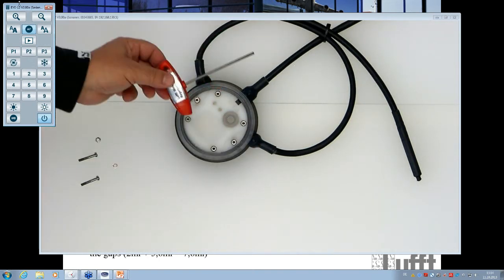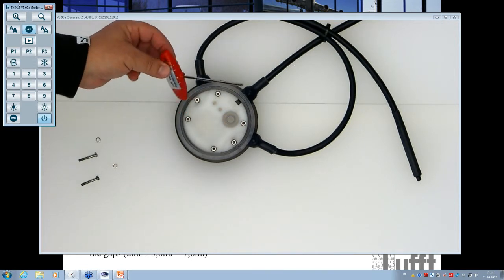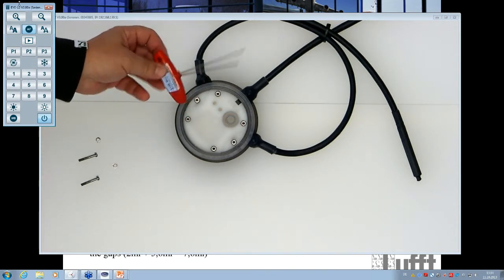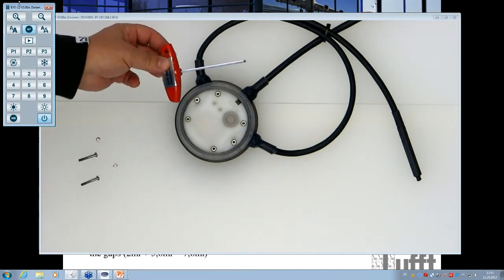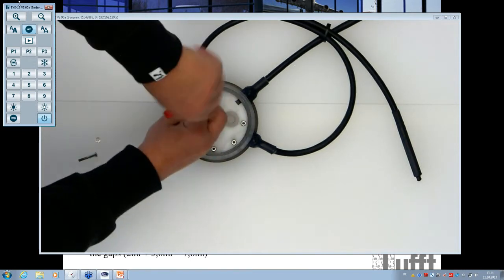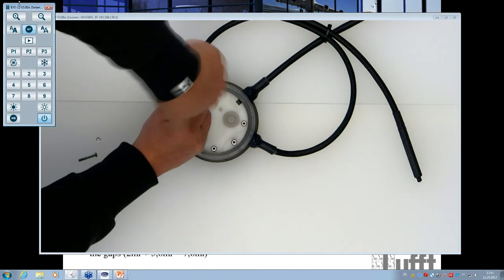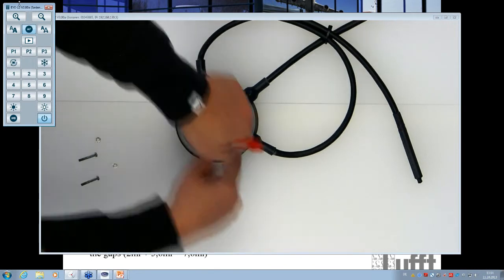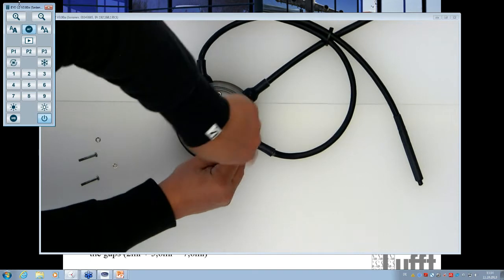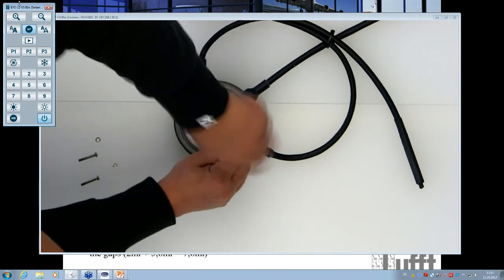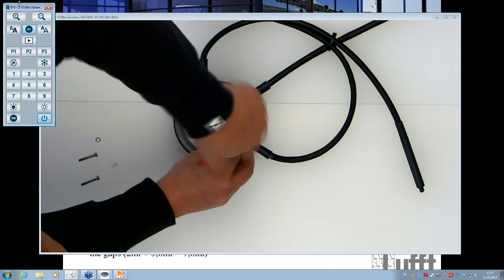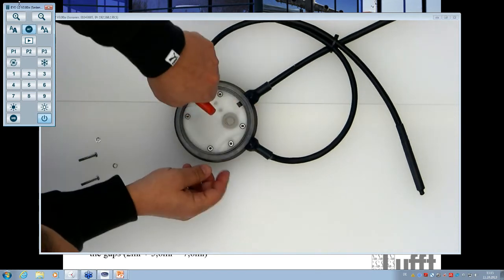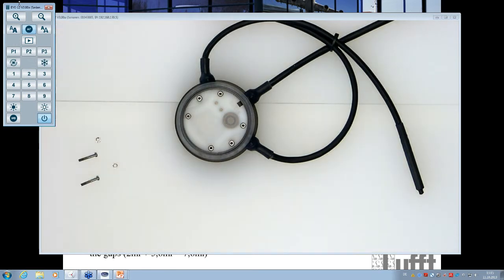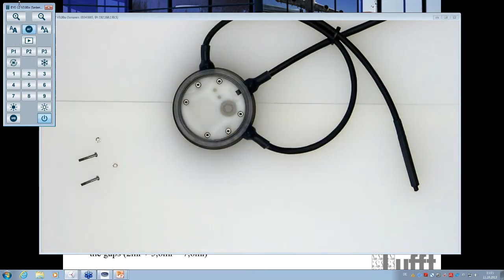It's a special key here. It's a hex wrench, size 3. Hex wrench, size 3 here. So fix it now. Don't fix it too strong so that maybe the plastic ring will break. It's only needed to fix it. You will see the sealing will attach to the surface, and that's okay. So that's enough. Now the water cannot escape anymore from the sensor itself. So that's the first step.